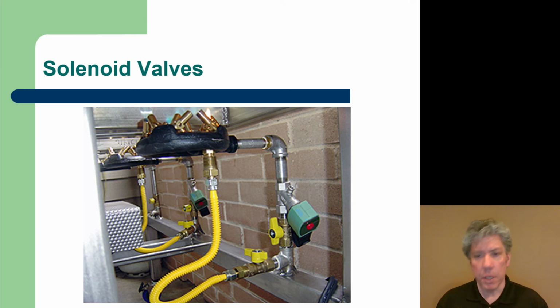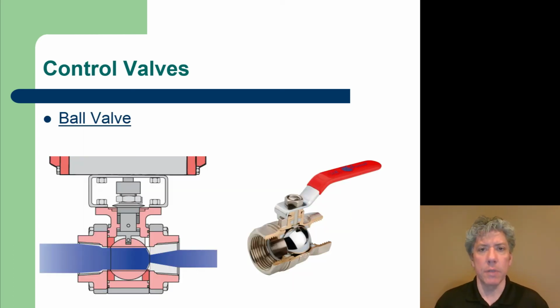Now here's a picture of solenoid valves being used to control gas flow to some burners. So here all you'd really need is on-off control. Other control valves are ball valves, and it's pretty common to have hand-operated ball valves. There are also electrically operated ball valves. And the way they work, you can see the cross-section on the right.